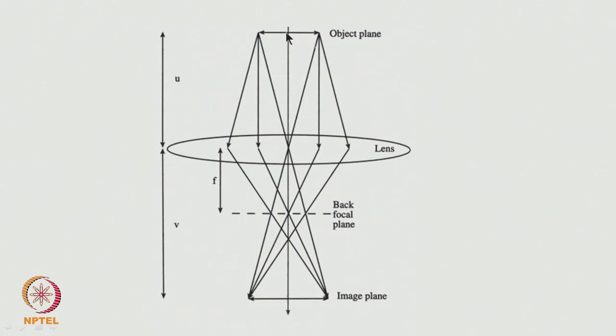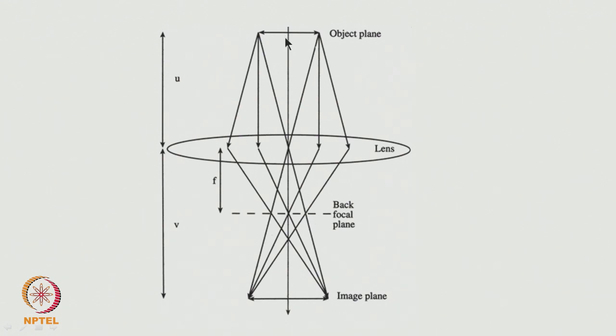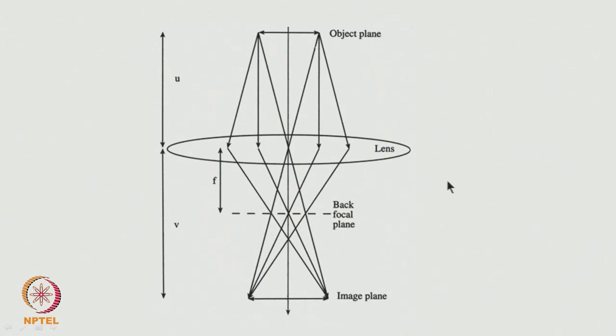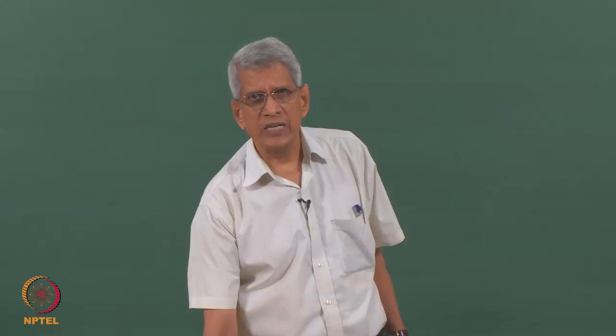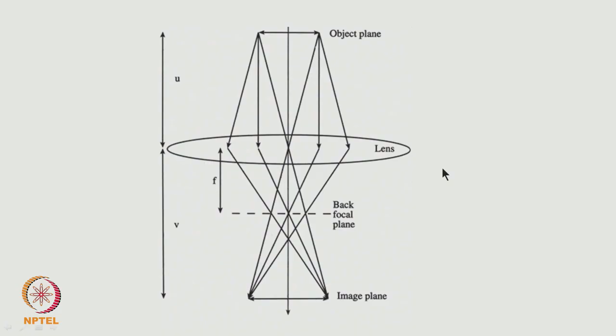By placing apertures either in the object plane or in the image plane, we can decide from which area we want to get the diffraction pattern. Choosing an aperture limits the region from which we get both the diffraction pattern and the image, which is why in an electron microscope we can get both diffraction and microstructure from the same area of the sample.